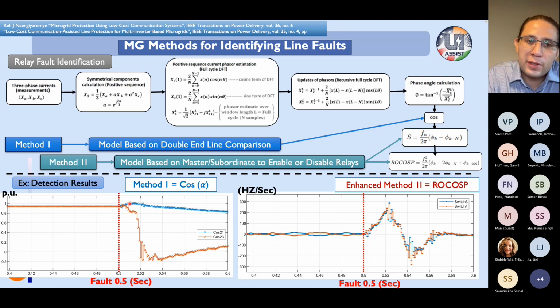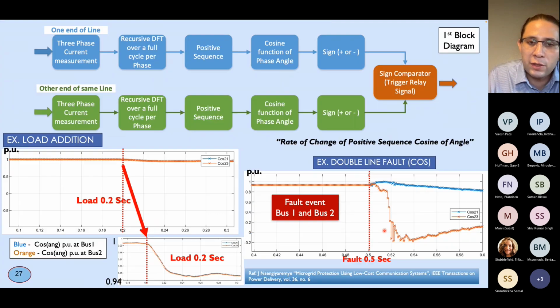Then the second method we implemented is the model based on a broader communication system, in case the cosine won't detect specific cases that we may face in daily life. So this system includes a bigger communication system, so actually more devices are connected additionally to the original ones mentioned. And we tested basically the slope over 2 cycles, and we tested the ROCOSP over 3 cycles. So I will explain this a bit later in the following slides. But basically, as we can see, when we have a fault at 0.5 seconds, due to the disturbance, we are able to identify a fault, which doesn't happen in normal operation.